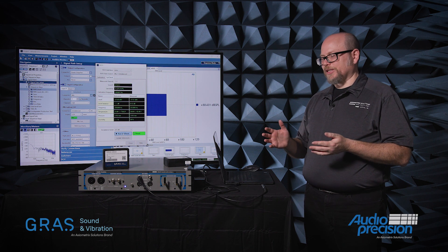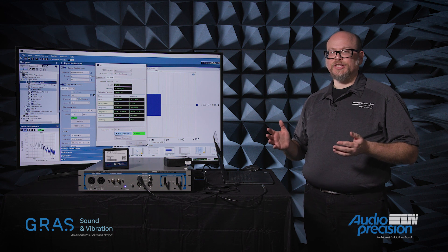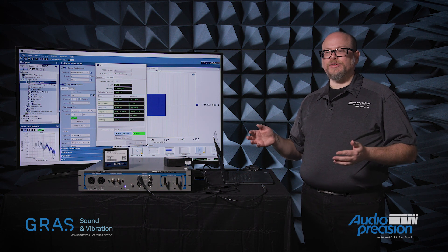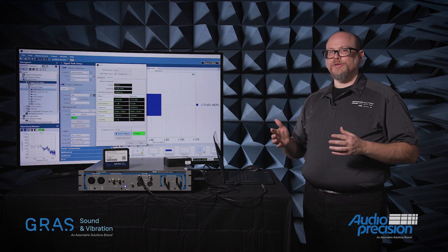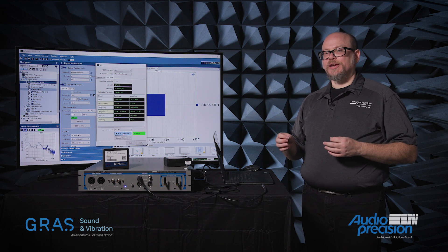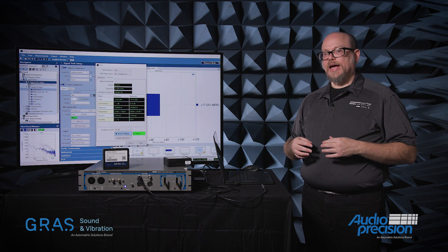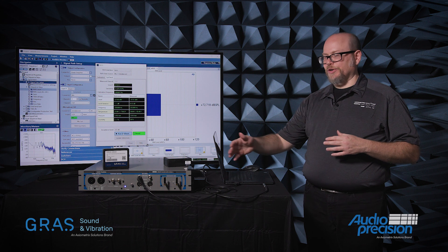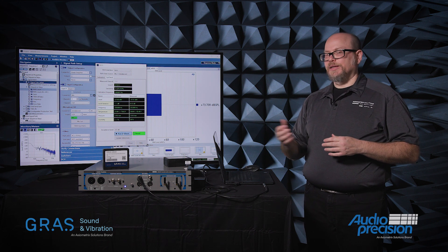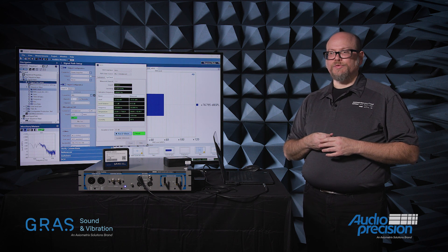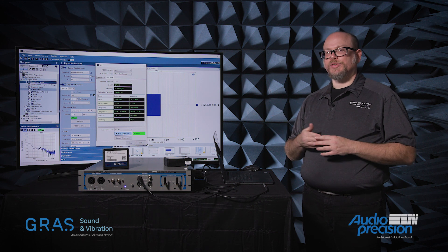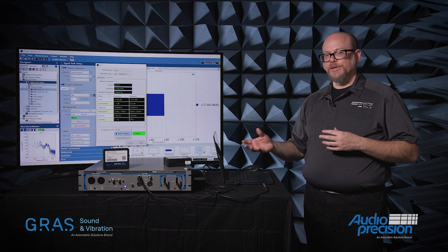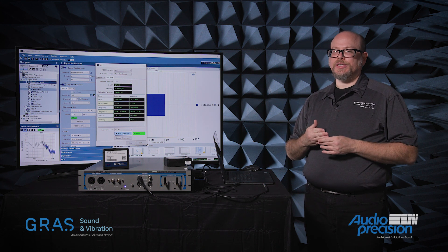The virtue of this is that potentially this microphone is not in a place that's easily accessible to me. Perhaps it's installed in an array, or in a test fixture in a production environment, or just inside of a large chamber while you're standing outside where the computer is located. In all those situations, SysCheck 2 allows us to verify the accuracy of the entire signal chain without having to have physical access to it. So I've not only verified the sensitivity of the microphone, but explicitly I've also verified the cable between the microphone and the analyzer, and even the analyzer itself — by measuring that reference voltage, I've verified it as well. I can now have a hundred percent confidence that my analysis system is working correctly, with all the benefits of doing a manual calibration with an acoustic calibrator, but without having to physically touch anything.